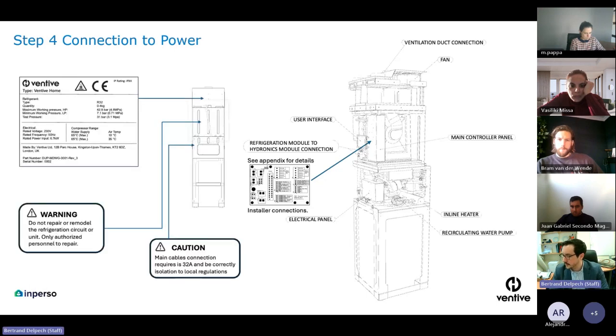This is just to show you where the ID plate of the system is. It's located on the top on the AHU, and I think there is one also in the lower section of the heat pump at the front. The main cable connection, 32 amp, it is very important that we have this type of supply to the system. The heat pump runs on a 1 to 1.5 kilowatt compressor.